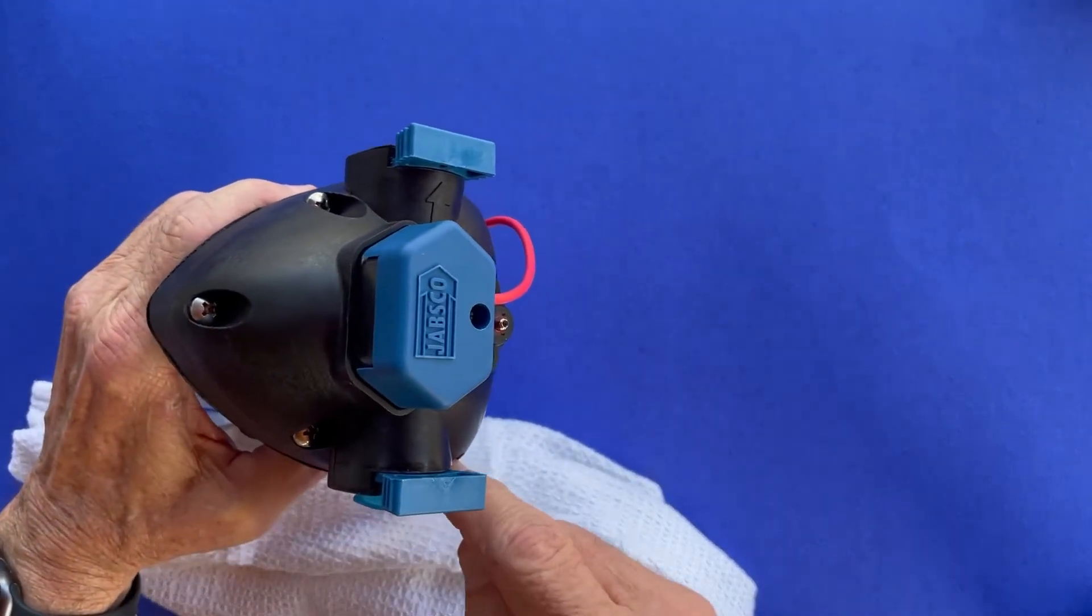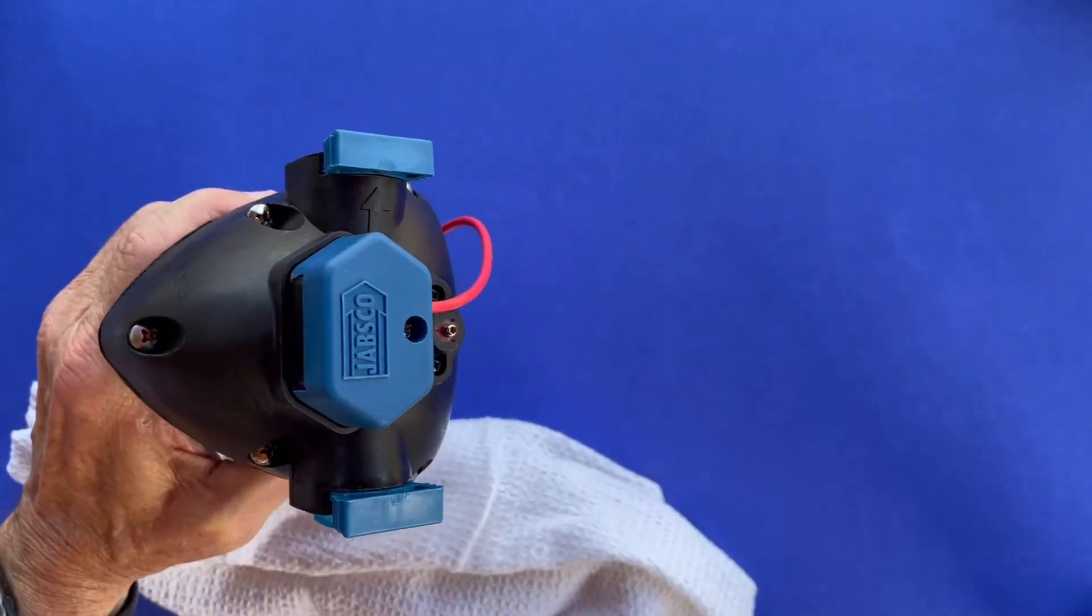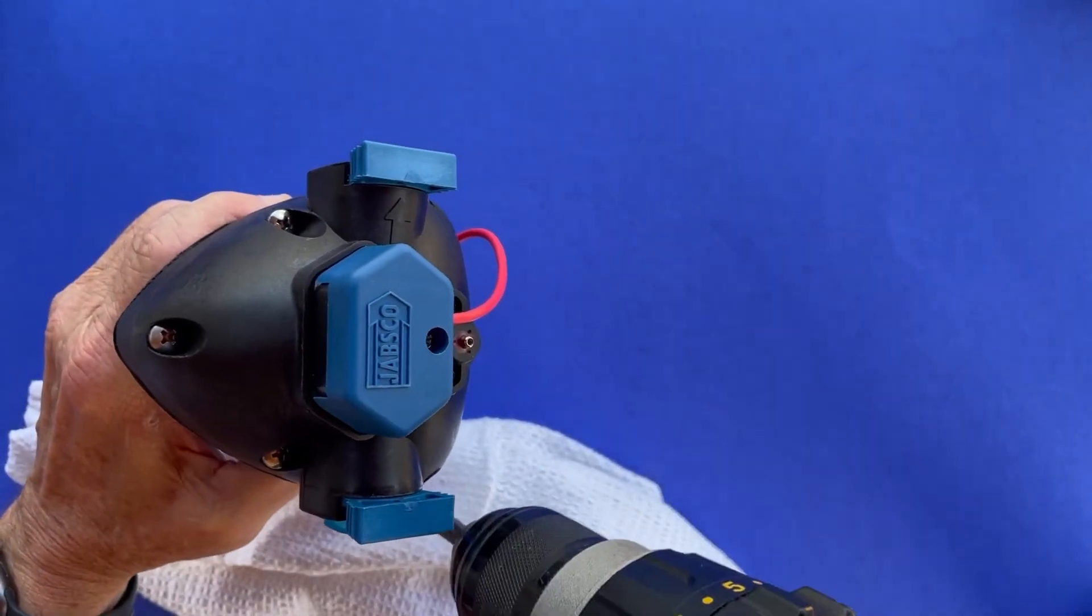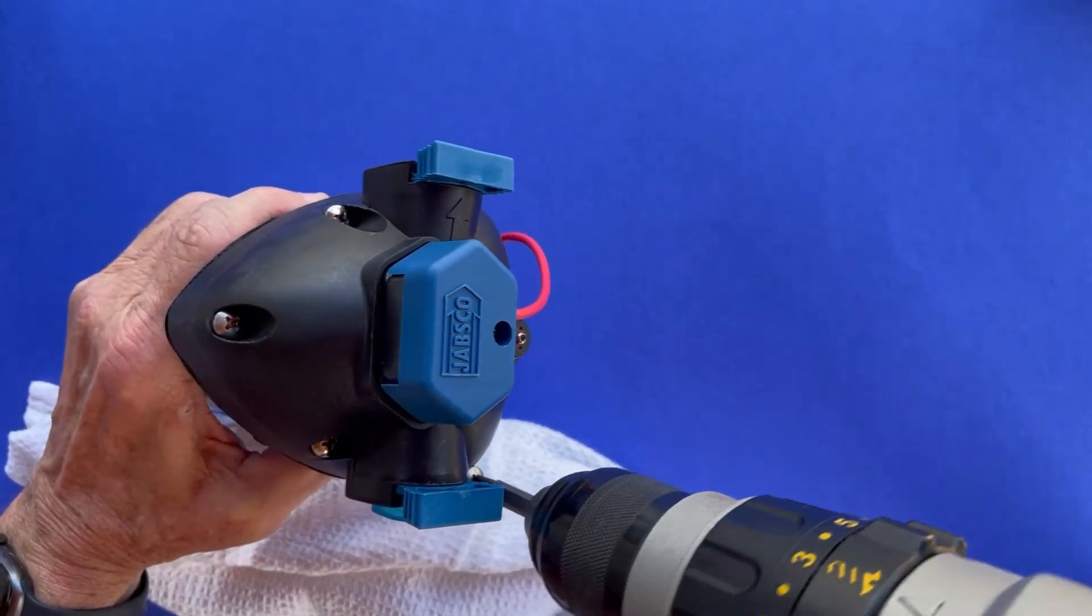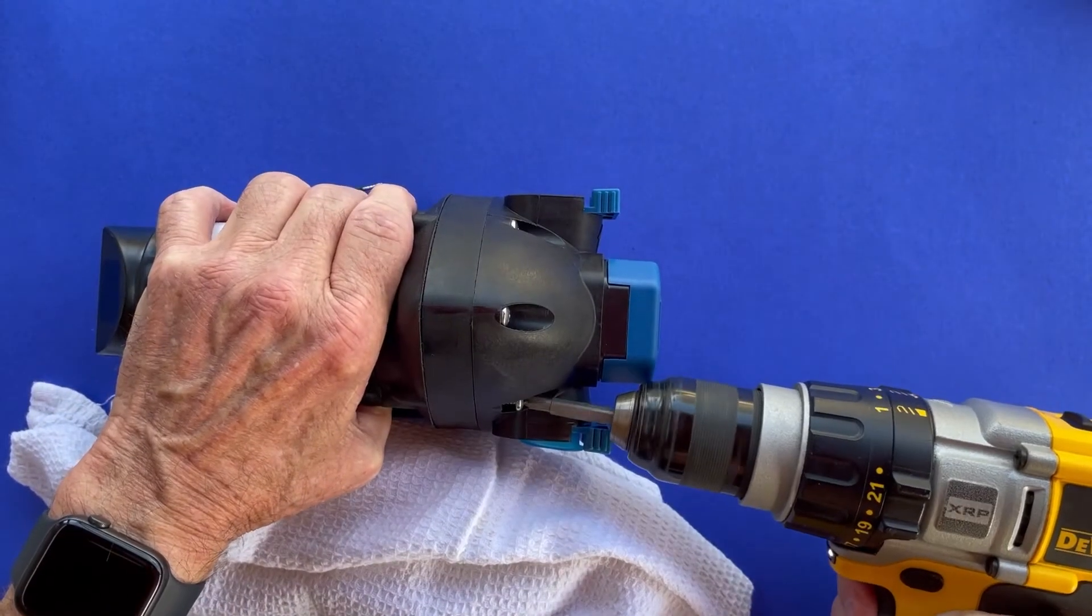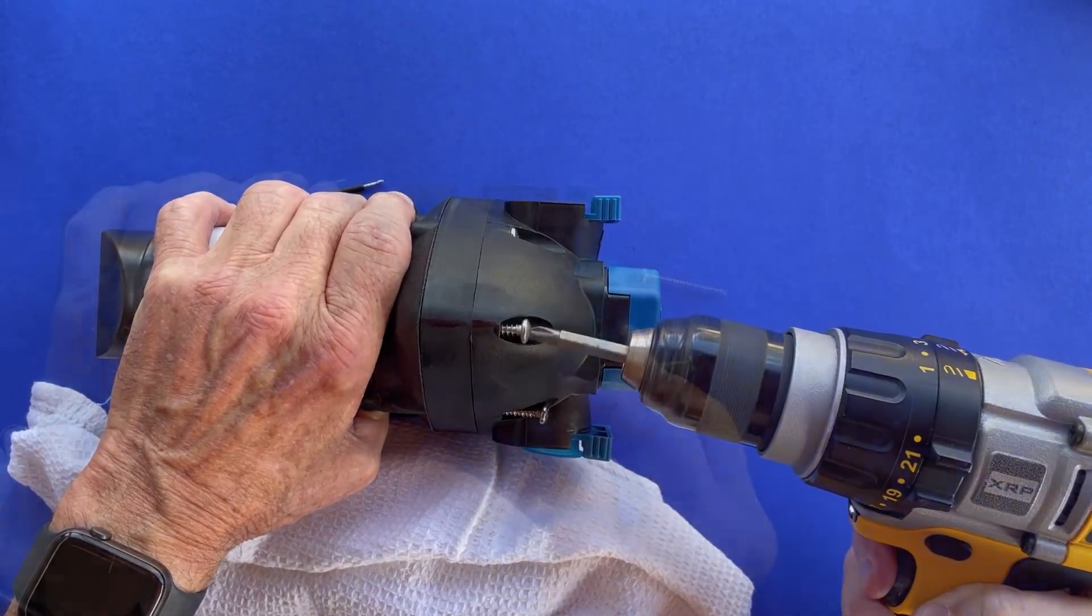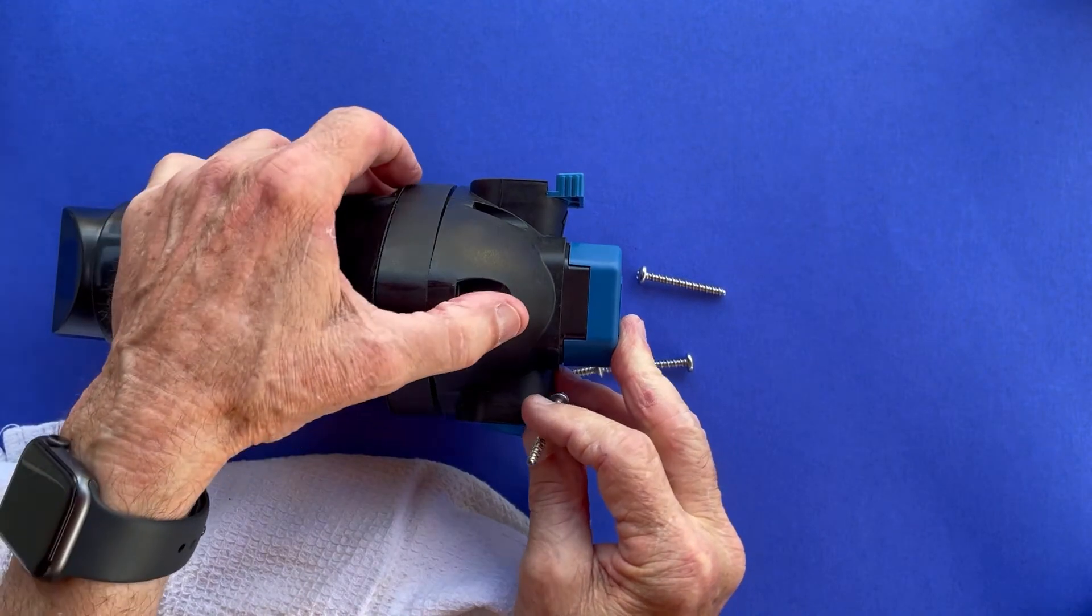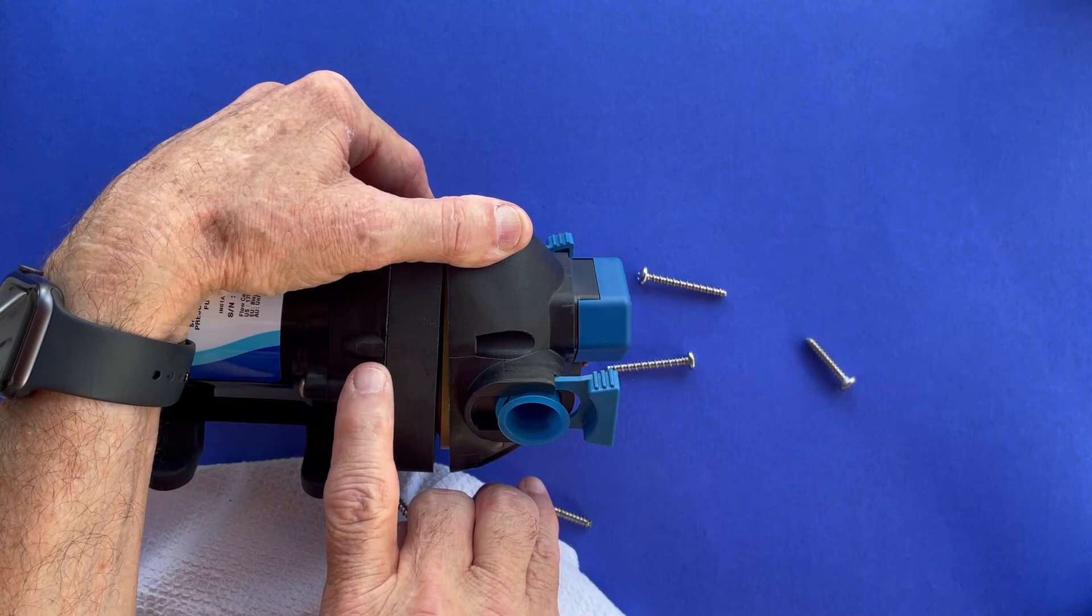Unscrew the six screws in the pump's upper housing using a Phillips head. Be sure to have a towel handy for any water that leaks out. Notice the three longer screws in their location. There is a plastic post on the housing for the longer screws.